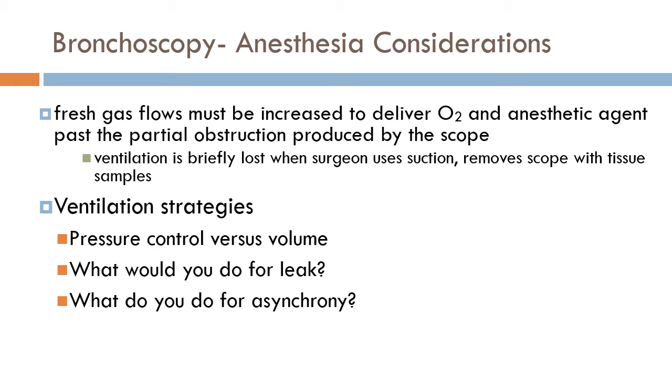You know, when you described it, then it won't work to stop the leak. It'll only give the 500 and cut the pressure off. But if it's not getting the 500 back because of the leak, then it's going to constantly start adjusting until it overshoots it by giving 700 minus your leak, and then it gets back 500. But all it's really looking at is, did you get the 500? So it's like yes and no, like I'm not sure.